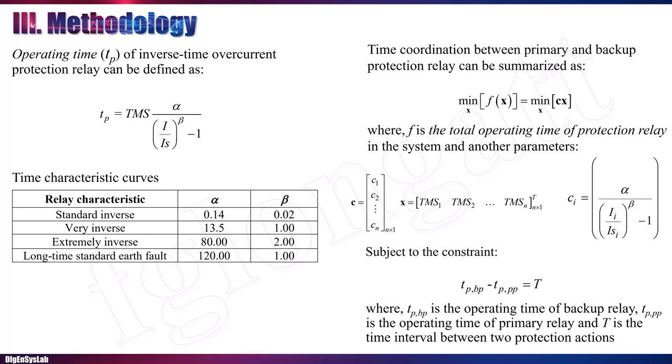For instance, using standard inverse, very inverse, extremely inverse, or long-time standard curve shapes, you will have characteristics with different shapes based on parameters alpha and beta. What we want to do in this paper is define a methodology to create coordination in several relays in a radial topology, and define the main indicators of the inverse curve — in this case the TMS and the time separation between devices.